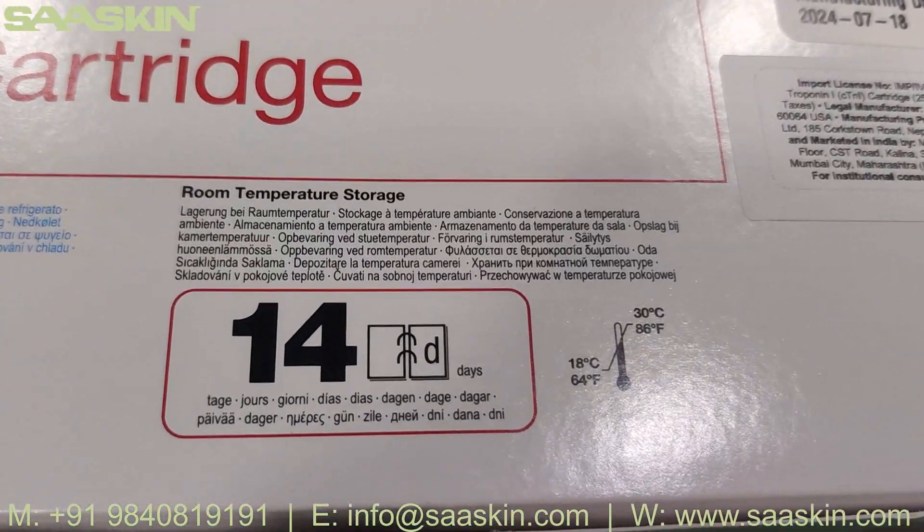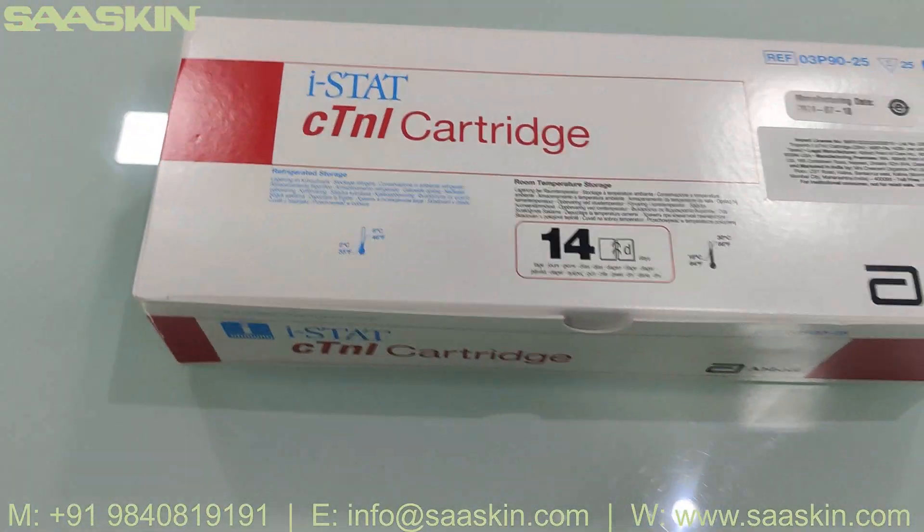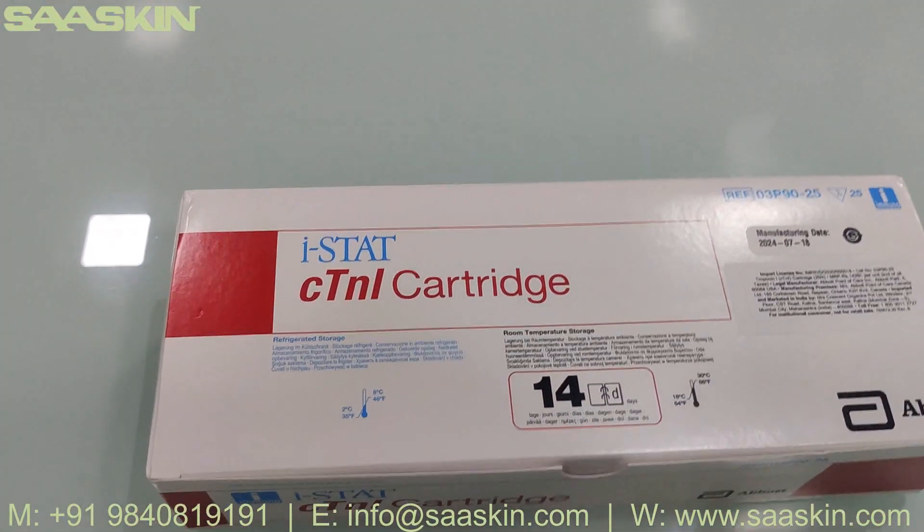This can be stored at room temperature for 14 days unopened, and the control should be maintained at 2 to 8 degrees Celsius. If you look at this i-STAT cTnI Cartridge...